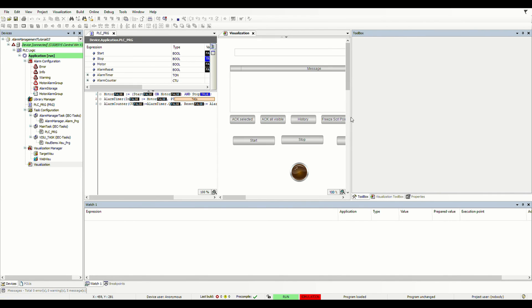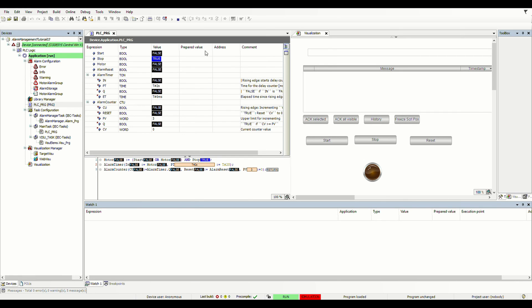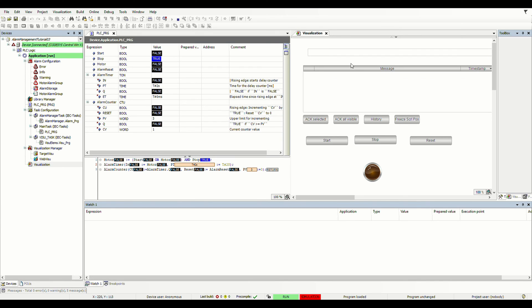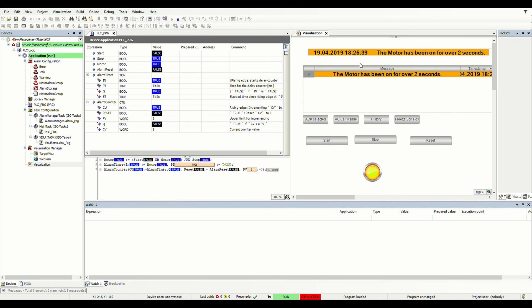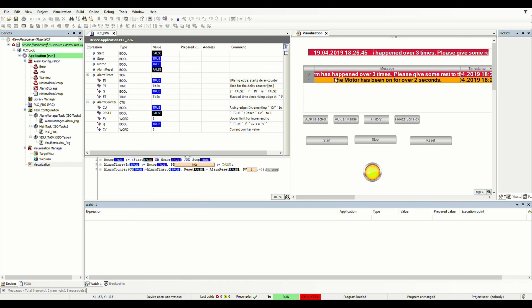I bring the visualization here so I also have access to the code and can see the values for different variables, including the alarm timer and alarm counter. Pressing start, the motor will turn on and after two seconds we will receive the first alarm in the form of a warning — the message is displayed there. Pressing stop, the alarm disappears because we no longer have the alarm condition. Starting again, the alarm comes back. When we have the alarm for the third time, the second alarm appears as well — in the form of an error with a red background and white text.